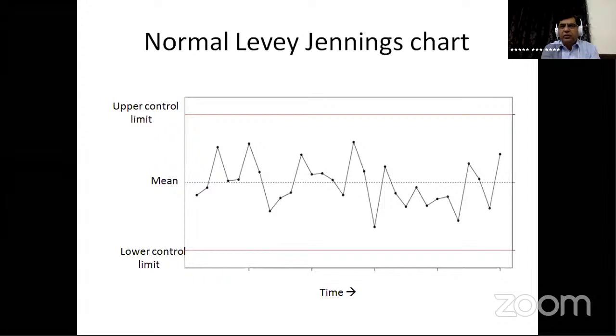This is an example of a normal Levey-Jennings chart where you can see the upper control limit in red and the lower control limit also in red, and a dotted line in the center indicating the mean. The observations, the values which we find from the machine on a daily basis are plotted, and you can see some values are near to the mean, some are away from the mean, but all the values should fall between the upper and the lower control limits.